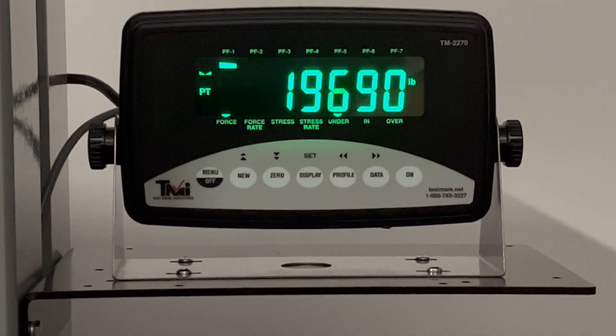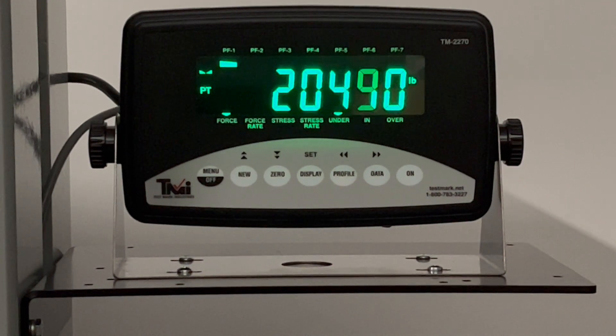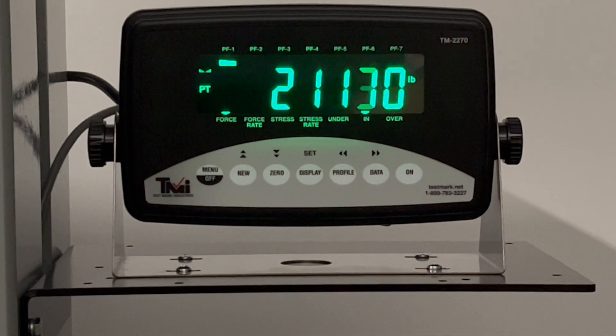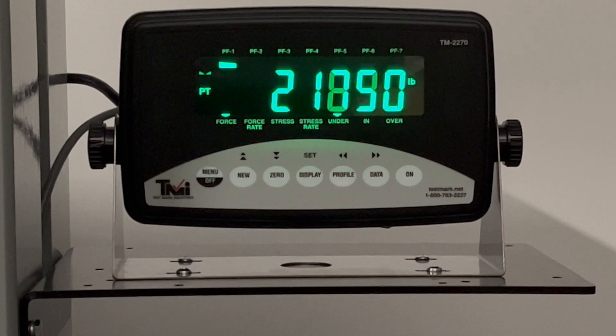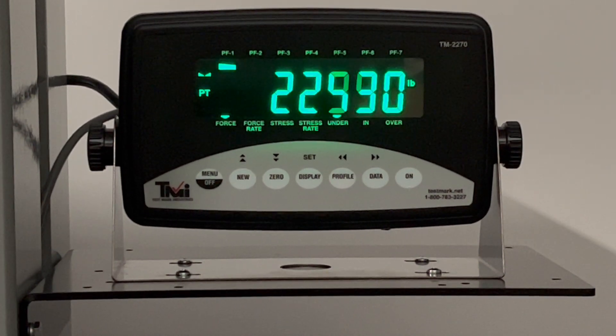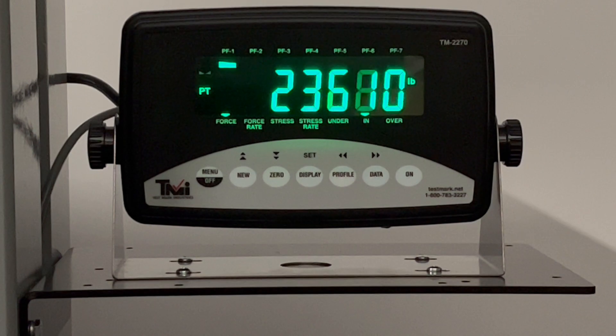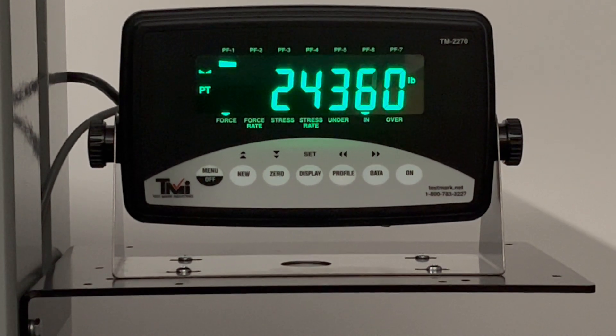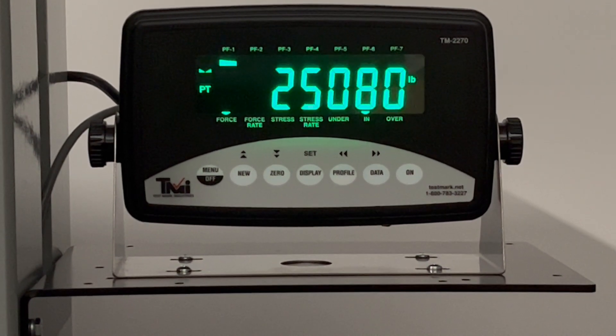As you can see on the screen, there is an under, an in, and an over indicator. If a sample is running too slow, a light comes on above the under. At the correct speed, the light is on above the in, and if it is running too fast, it is above the over.